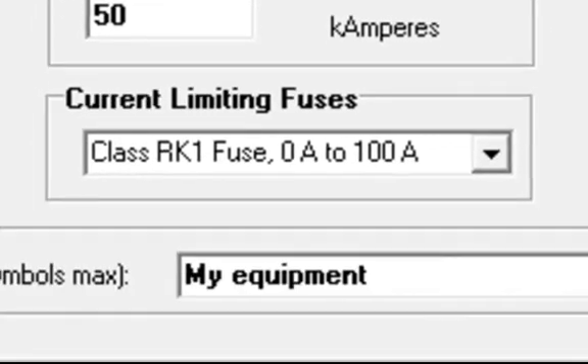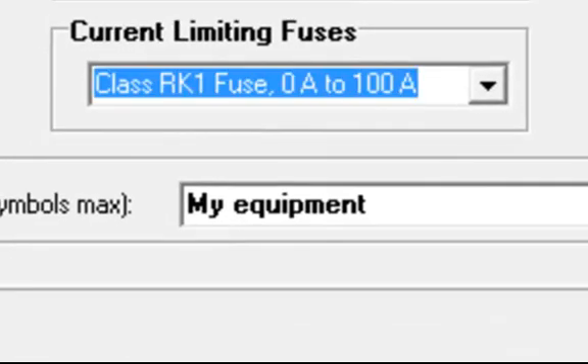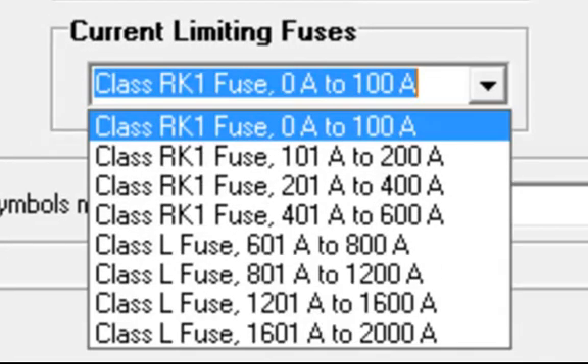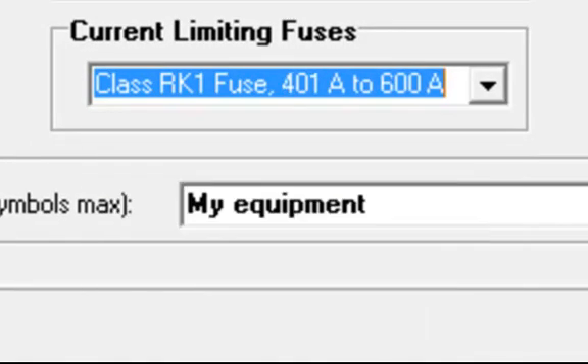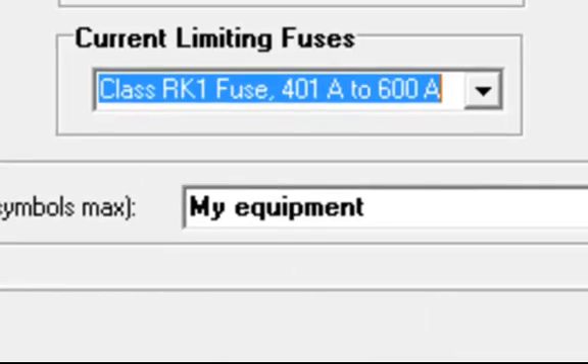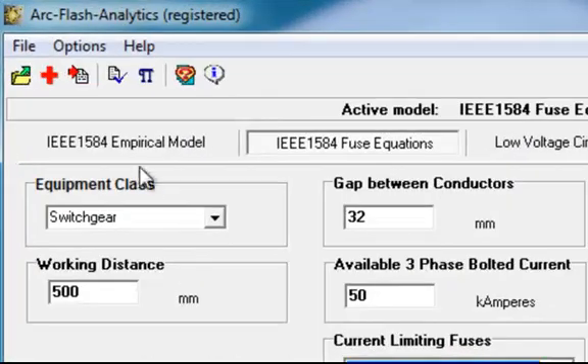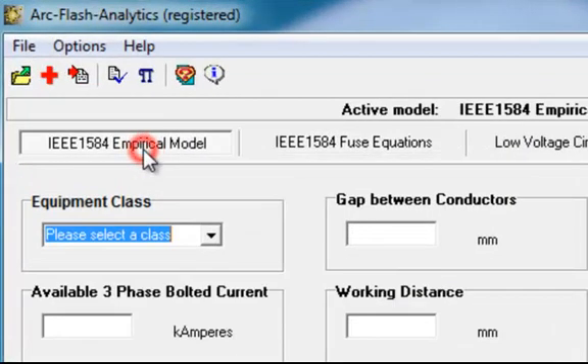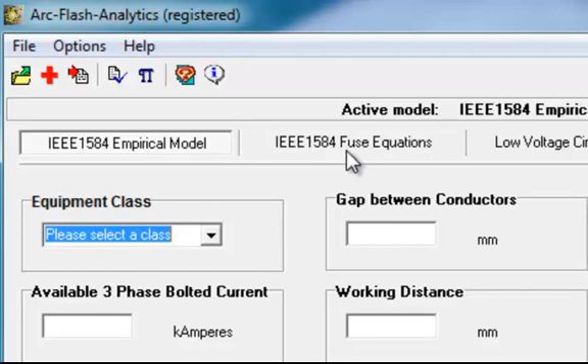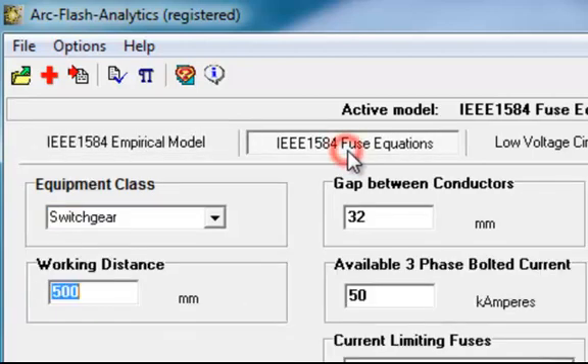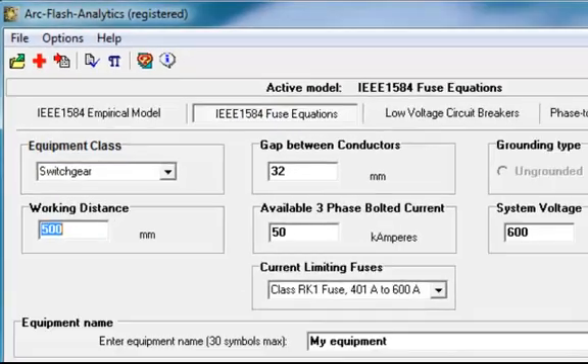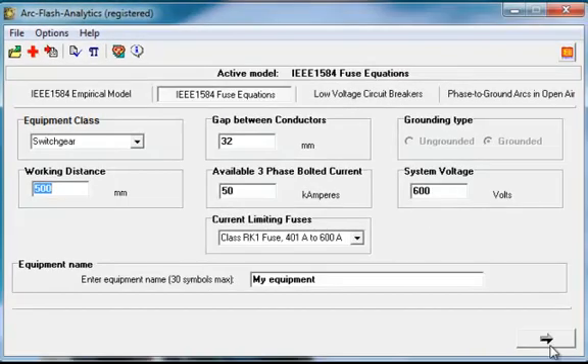The program will automatically substitute grounding type, system voltage, and gap between conductors 32 millimeters or 1 1/4 inches when in IEEE 1584 Fuse Equation Mode.